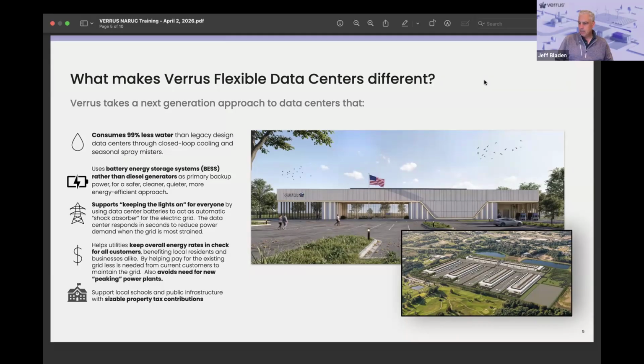Just by way of reference, there are a few other things that differentiate our data centers, including more efficient cooling systems that consume dramatically less water, and the ability to use battery energy storage to support the grid when it's stressed in multiple ways. In our case, we're designing our flexible response capabilities around the NERC reserve standard—everything from primary reserves, sometimes called capacity, which is what the MISO capacity market we were just talking about procures, to other contingency management solutions sometimes called ancillary services, ranging from a few seconds response to 10-minute or 30-minute response.